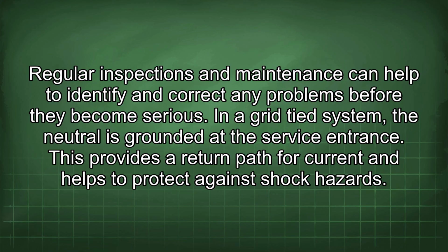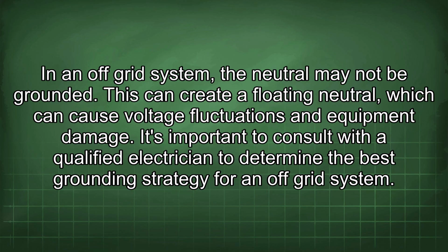In a grid-tied system, the neutral is grounded at the service entrance. This provides a return path for current and helps to protect against shock hazards. In an off-grid system, the neutral may not be grounded. This can create a floating neutral, which can cause voltage fluctuations and equipment damage. It's important to consult with a qualified electrician to determine the best grounding strategy for an off-grid system.